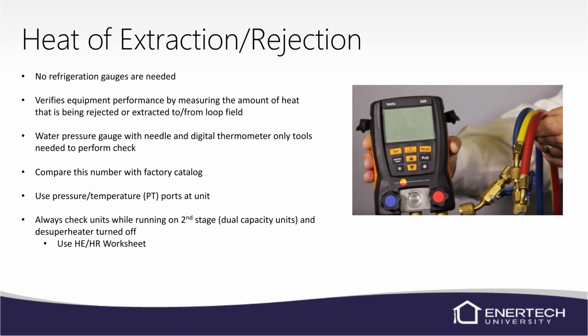Obviously, we've got to have pressure temperature ports. When you call into tech support, one of the first things we're almost always going to ask you is your water flow rate. If you tell us, well, I don't have pressure temperature ports and it's on a pressurized flow center, there's no way to establish water flow, and we have to have water flow before we can really do anything. So we want to make sure that whenever you're installing a unit, you always install pressure temperature ports. If you've got a water-to-water unit, make sure you put them on the source and the load water piping, because we'll want to check water flow on both. So when in doubt, put a pressure temperature port in. They're cheap and they'll save you.